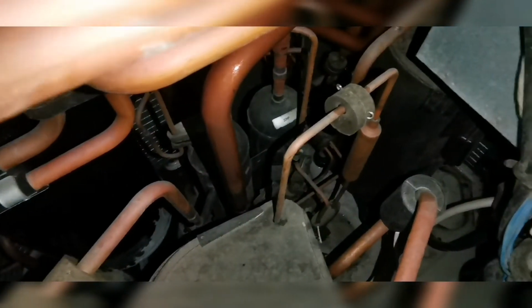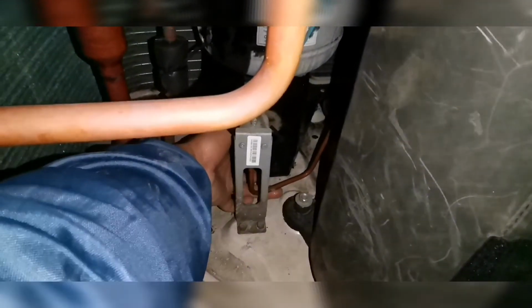would be our oil separators and the capillary. So checking your temperature differential is very important. The same goes for checking your temperature differential on the accumulator return valve. So luckily for us, we've got clamps. We can put the clamps on here and actually get an accurate measurement.